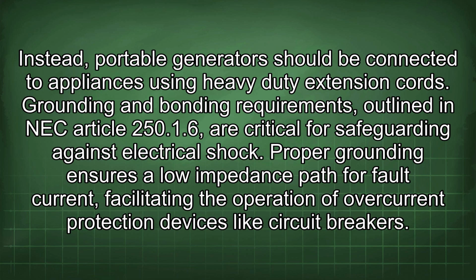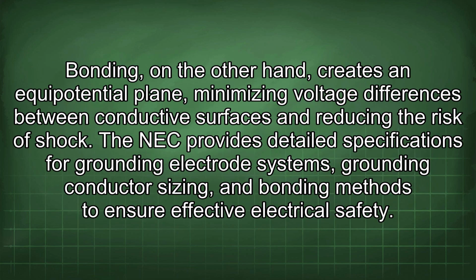Grounding and bonding requirements, outlined in NEC Article 250.16, are critical for safeguarding against electrical shock. Proper grounding ensures a lower impedance path for fault current, facilitating the operation of overcurrent protection devices like circuit breakers. Bonding, on the other hand, creates an equipotential plane, minimizing voltage differences between conductive surfaces and reducing the risk of shock. The NEC provides detailed specifications for grounding electrode systems, grounding conductor sizing, and bonding methods to ensure effective electrical safety.